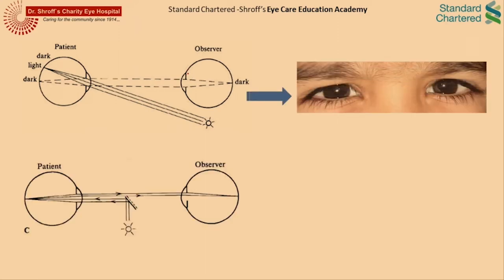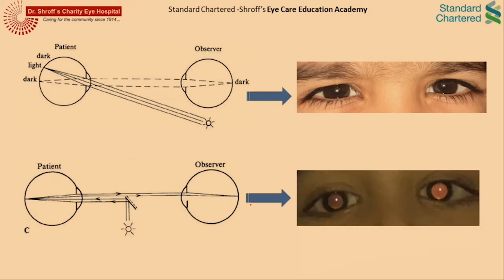This problem was overcome by the inventors of the direct ophthalmoscope. In this device, the light is projected onto the examinee's eye after reflection from a semi-reflective mirror, a mirror with a hole, a partial mirror, or a prism, thereby enabling a part of the reflected light to reach the observer's eye, thus capturing the red reflex and even enabling examination of the fundus.